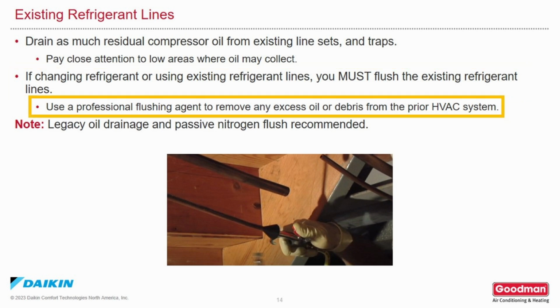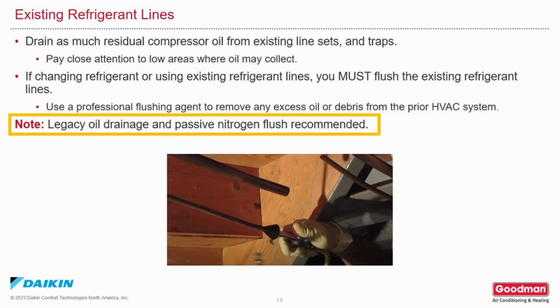If the new unit you are installing uses a different refrigerant than the one that was existing, you must flush the existing refrigerant lines with a professional flushing agent to remove any existing oil, debris, or refrigerant. Draining the legacy oil from the system and using a passive nitrogen flush is recommended.